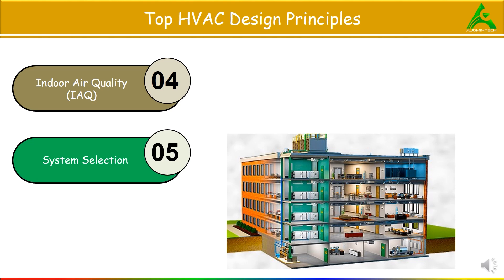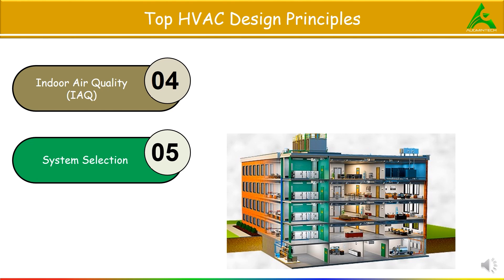The fifth design principle is System Selection. Here we choose an HVAC system that matches the building usage, climate, and budget for optimum performance. For example, a shopping mall in a tropical climate requires a chilled water system because it handles large, consistent cooling loads effectively and is cost-efficient for a central plant serving multiple zones. The chilled water system allows for scalable cooling, ensuring comfort for shoppers even on peak days.